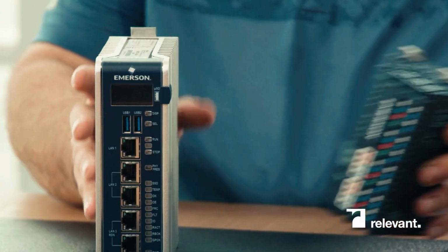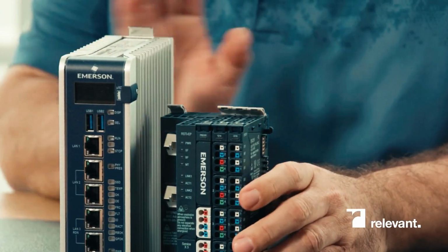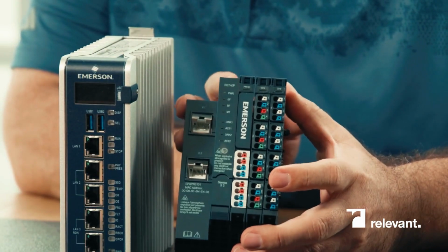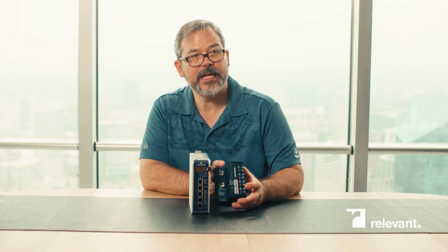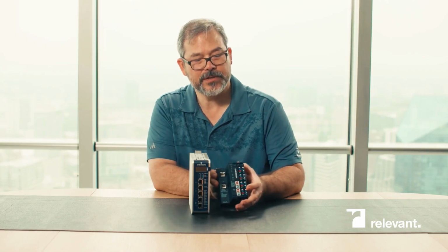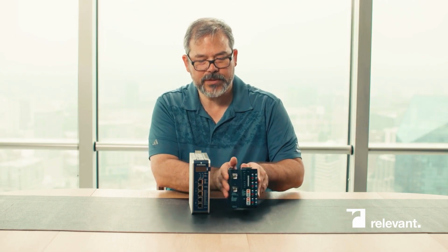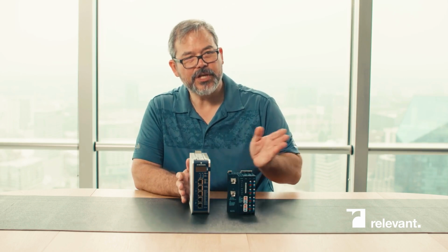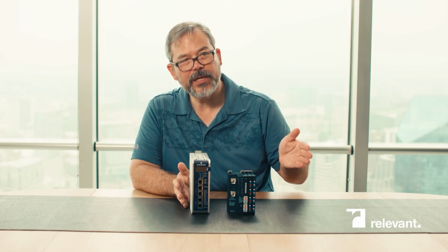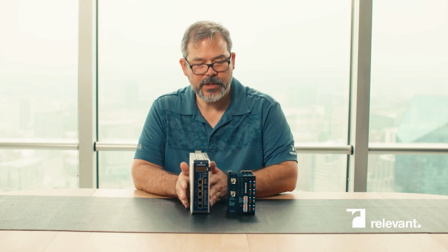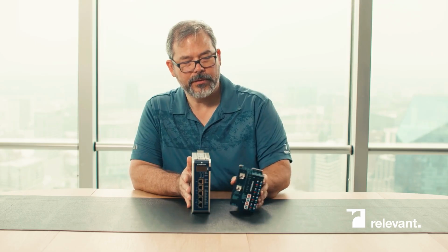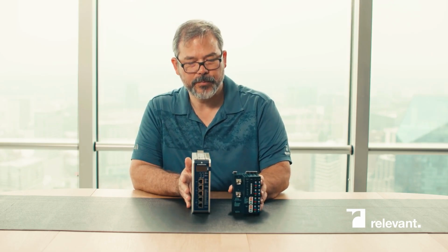So you'd have the controller connected to some sort of distributed I/O, like our RSTI EP slice I/O on Profinet. Right here I've got a Profinet scanner with a couple of I/O points, and then we could daisy chain several I/O drops, or we can add in many different I/O slices to create a singular controller with distributed I/O.